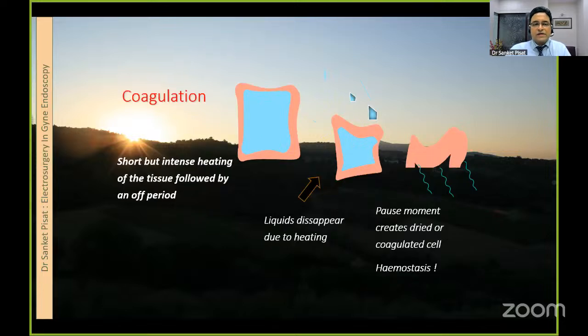When we move to coagulation, there is a short but intense heating of the tissue, which is more or less the same as cutting. But in coagulation, this is followed by an off period, in other words, a cooling off period. What happens because of the cooling off periods? The liquids do not get superheated, they get time to dry up. And when they get time to dry up, these liquids disappear. This pause creates a dried or coagulated cell, which then results in hemostasis. So, same current, but deployed in different ways, resulting in different actions on the tissue.